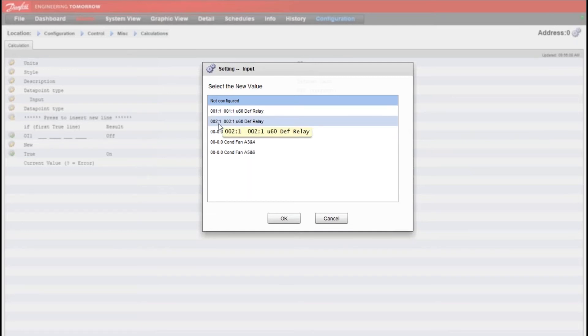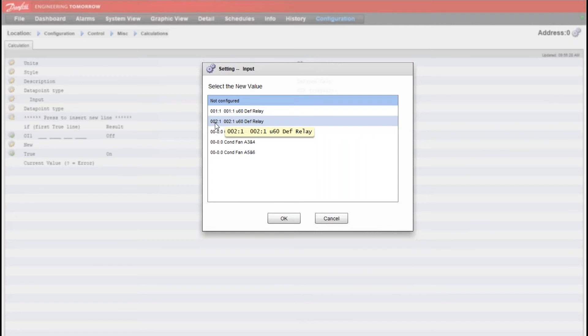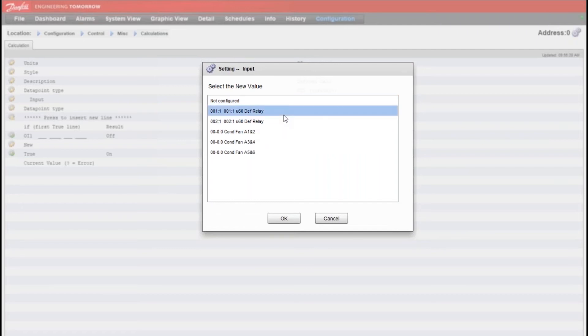The formatting of the points here, so 1 colon 1 would mean this is my first case controller which has an address of 1 and it was the first data point that I imported or the first OI specific data point that I imported from that case controller. Similarly, case controller address 2 and then the first OI data point I had imported from that one.